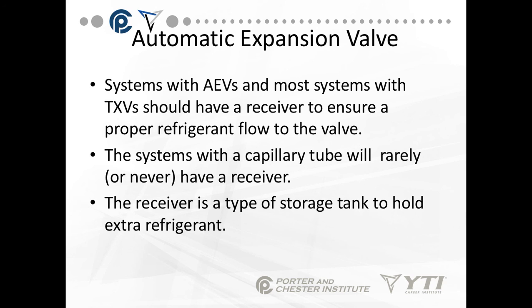Systems with AEVs and most systems with TXVs should have a receiver to ensure proper refrigerant flow to the valve — you cannot have vapor going to an AEV or TXV; it can only be liquid. If you have vapor bubbles going to your TXV, you're going to have improper refrigerant pressures. Systems having capillary tubes can handle some vapor bubbles, so they'll rarely have a receiver. The receiver is a type of storage tank to hold extra refrigerant.